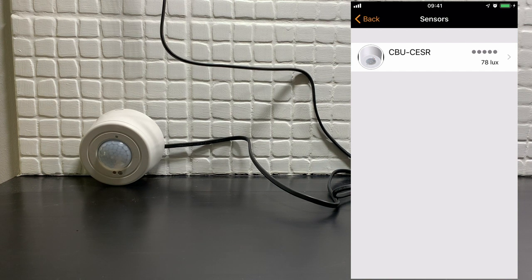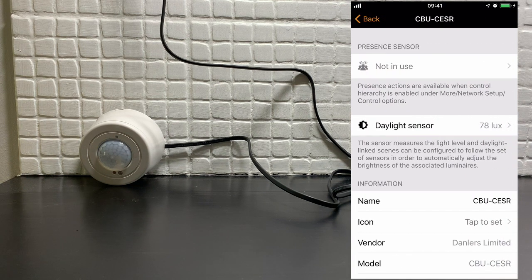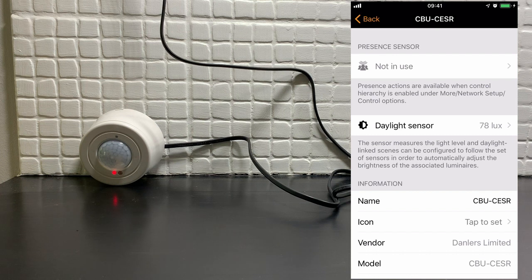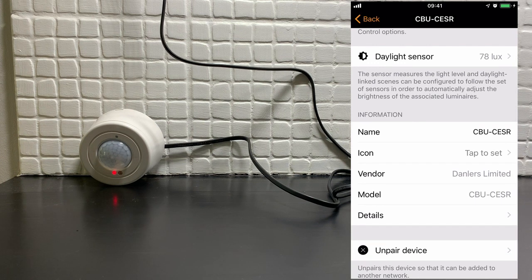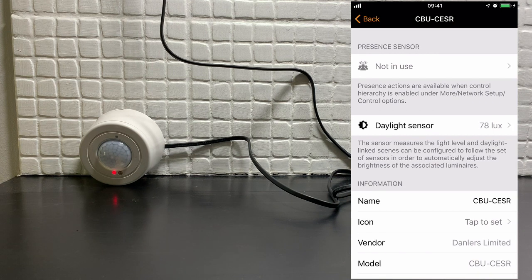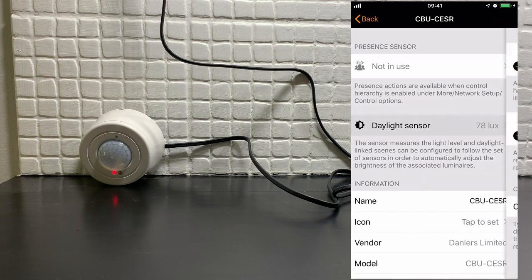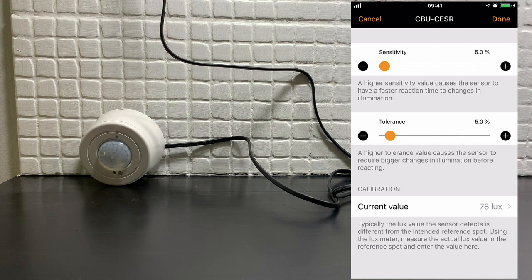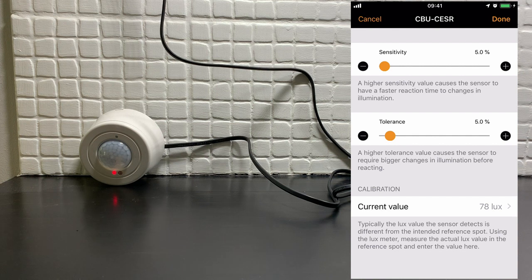If we select the sensor, for now we'll ignore the presence sensor options, we'll do that later on. As with any device you can change the name and change the icon. Selecting daylight sensor will also allow you to change the sensitivity and the tolerance of this particular sensor. If needed, selecting current value will also allow you to calibrate your sensor using a lux meter.